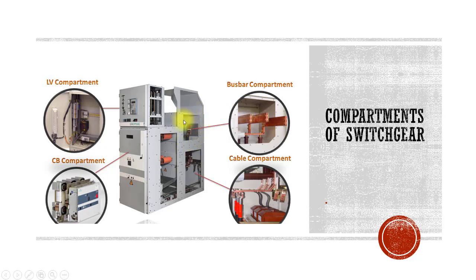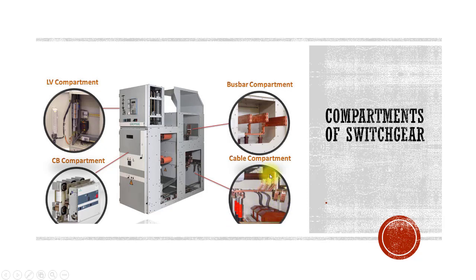On the back side you can see this is the busbar compartment. The busbar compartment looks like this. Coming down further, you will see this is the cable compartment. Cable entry is from the bottom in MV switchgear.